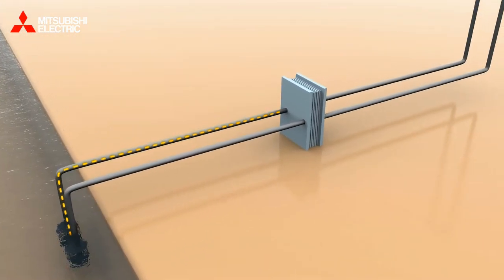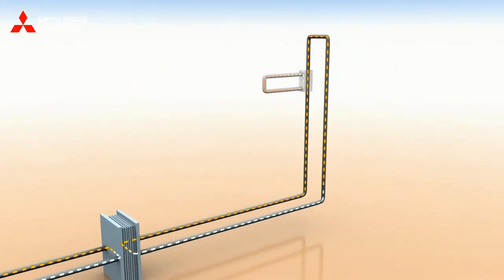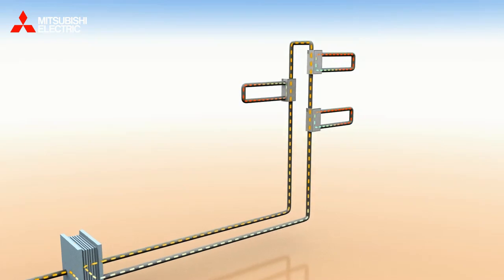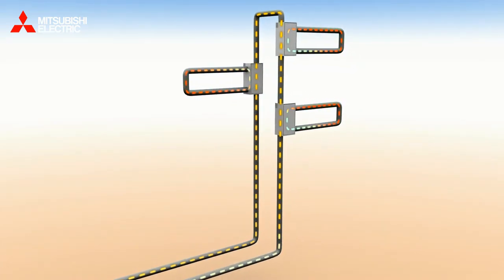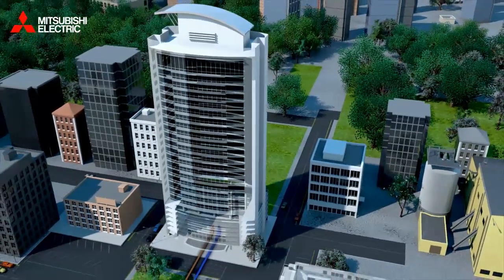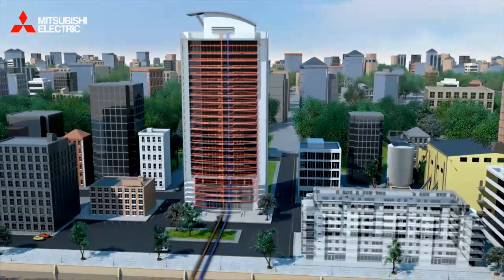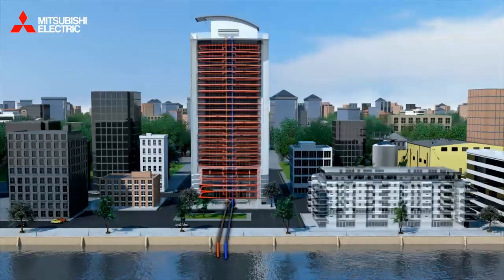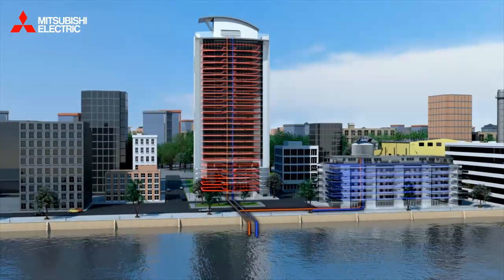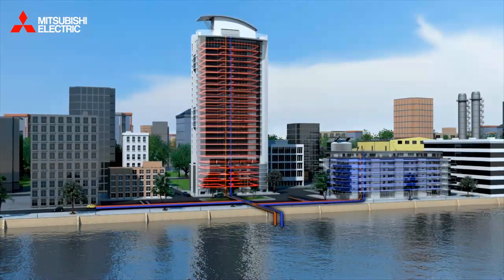In the case of an open water energy loop, low-grade heat is harvested from the river or lake and upgraded using heat pump technology to deliver hot water and heating to a building. This upgraded heat can then be further enhanced at an apartment or office level to deliver full control and individual billing. This is already being used in London, where heating is being delivered to over a hundred apartments built 200 metres from the River Thames. When the hotel alongside the development starts to operate, we will be able to see the full effect of a highly efficient energy loop as the heat recovered from cooling hotel bedrooms is used to deliver hot water to the homes next door.